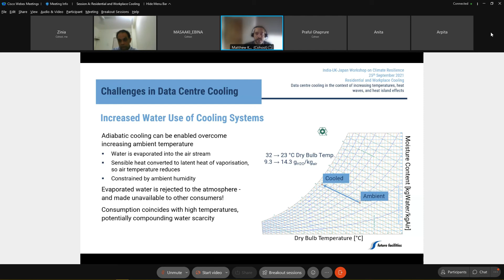In any case, this process, of course, uses water, as we can see on the right. And the water is often taken from processed sources, meaning that it already has embedded energy. And when it's rejected to the atmosphere with the airstream, it's obviously made unavailable to other consumers. And I think that's a particularly pertinent point in terms of heat waves, because during a heat wave, the adiabatic cooling systems are more likely to be in use for long periods. And that's actually going to increase the demand at a time where there's generally going to be increased scarcity.